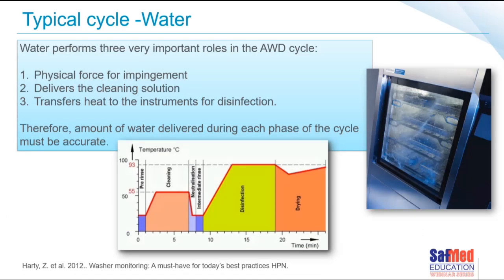Water performs three important roles in the automated washer disinfector cycle: it is the physical force for impingement, it delivers the cleaning solution, and it transfers heat to the instruments for the disinfection phase. The amount of water delivered during each phase must be 100% accurate. Water pressure is used to clean and rinse the instruments — this is also known as the impingement value: the mechanical force of water against surfaces inside the chamber. High impingement means water is sprayed at high pressure, while a low impingement washer relies more on chemistry to achieve the desired cleaning result.